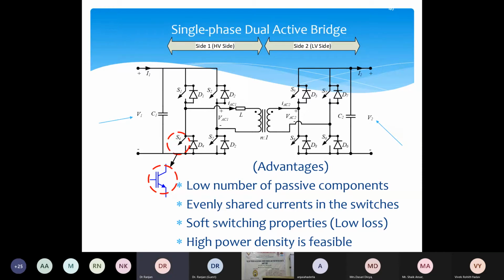You take a 50 Hz transformer. A 1 kVA 50 Hz transformer will have a size of at least 15 centimeters to 15 centimeters. Whereas a 1 kVA high frequency transformer will be less than 5 centimeters to 4 centimeters to 4 centimeters. This is the beauty of this converter - when you are designing it, it is very compact, so you can say these are compact power supplies.